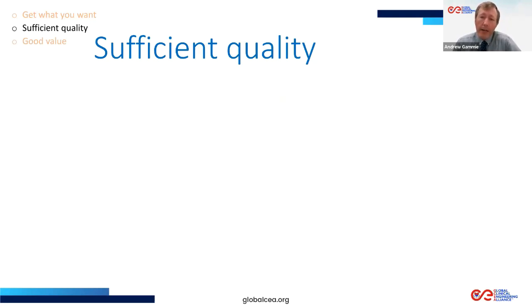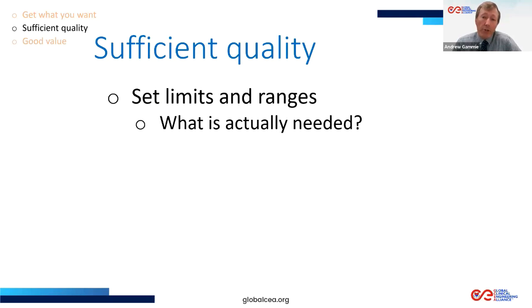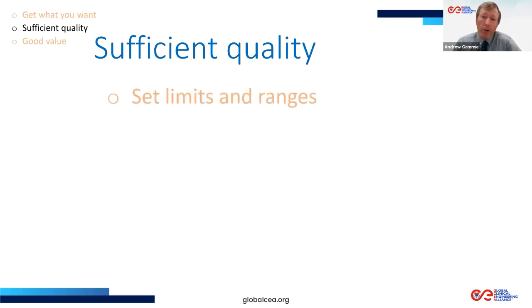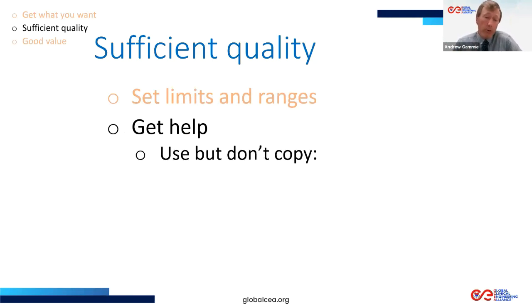By the way, in that, just for instance, don't use specific numbers, but use, instead of 3.6 millimeter tubing, say 3 to 4 millimeter tubing, get a range. And then you can measure it and get a better selection of devices, more bids that are acceptable. You can also get help to get this quality. When you're writing a specification, you can use specifications from elsewhere, but you can't copy them. You've got to edit them for local needs.